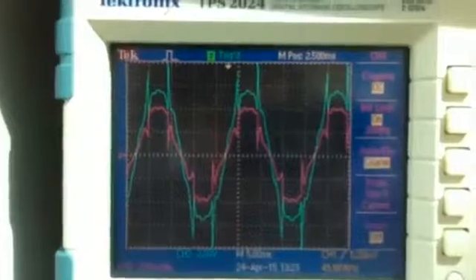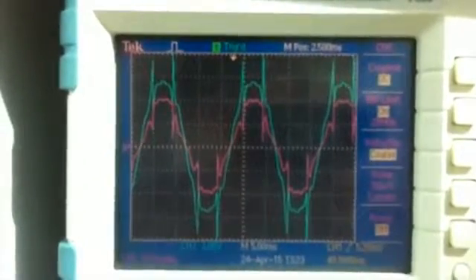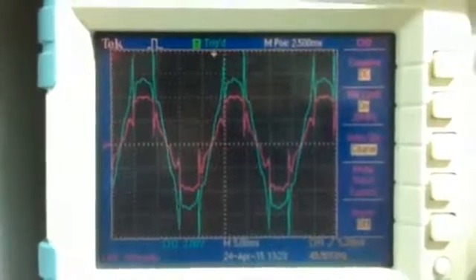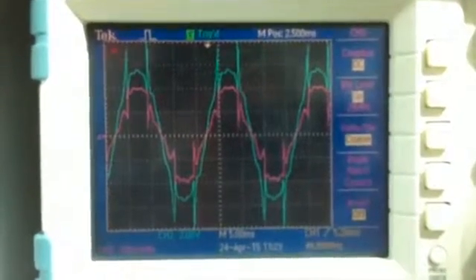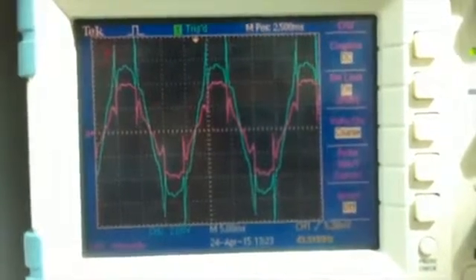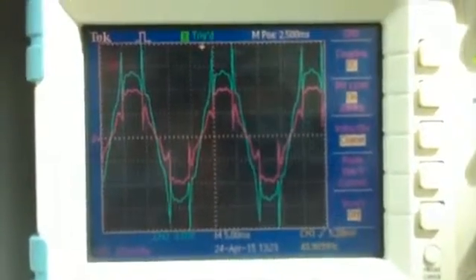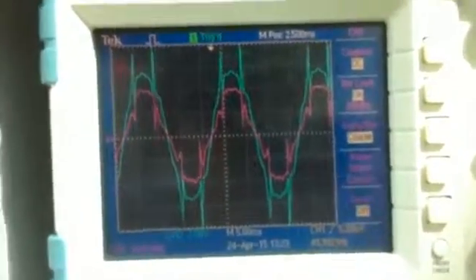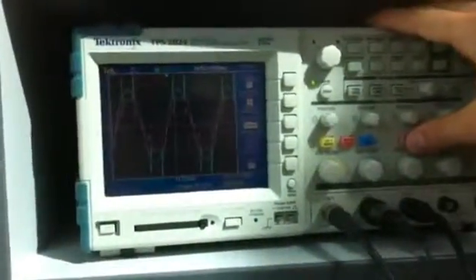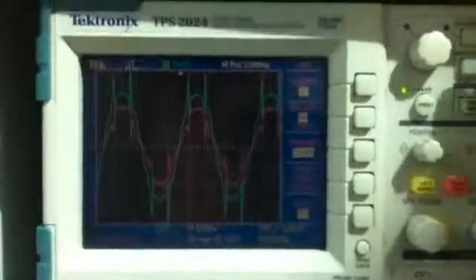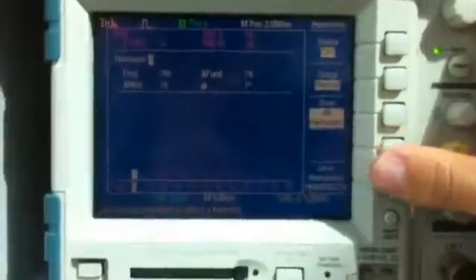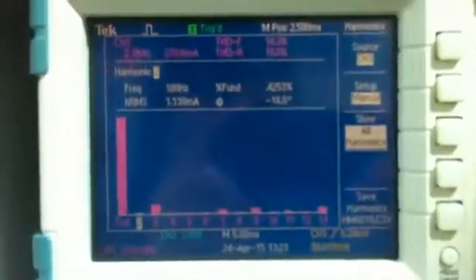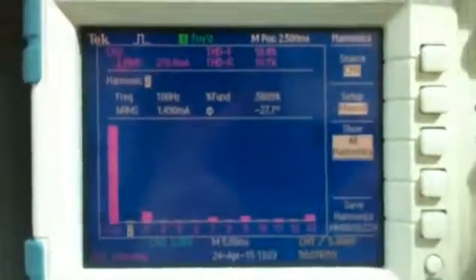So if you look at the spectrum when I apply this inductor, you can see that they are almost perfectly in phase now. So that's the addition of the inductor, which is acting like most capacitors which are used for power factor correction, except now we're doing the opposite, we're adding an inductor. Yeah, so that's the entire system, and if we look at the current harmonics after what I've called the compensation inductor has been added, this is what the current harmonics look like, and they've been significantly reduced. All right, yeah, that's it.